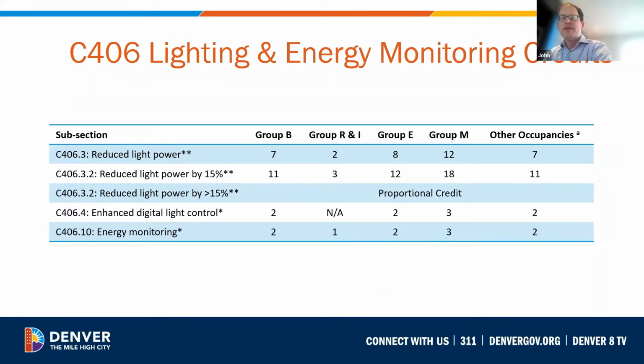Efficient lighting systems can provide a significant portion of the required credits, particularly for the retail or mercantile occupancy group. An interior lighting power reduction of at least 10% is required to claim a credit. Additional credit beyond C406.3.2 is allowed for lighting power reductions greater than 15% from the base allowance. This is referred to as a proportional credit because the credit can exceed the 15% for even additional energy credit levels. We'll review that as an example a little bit later in the training.